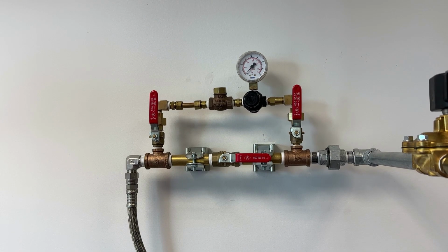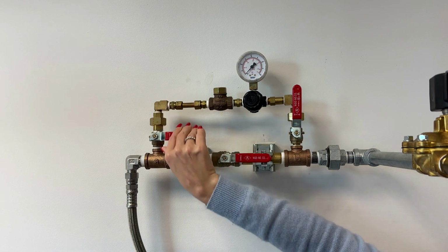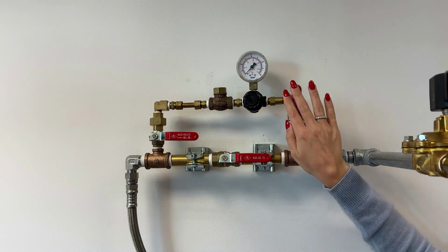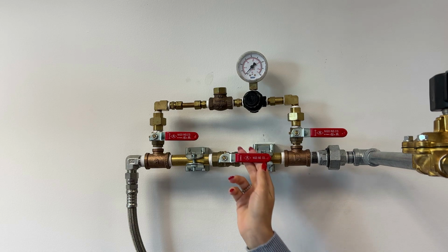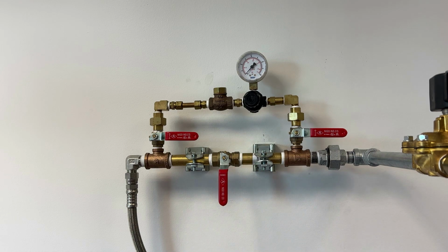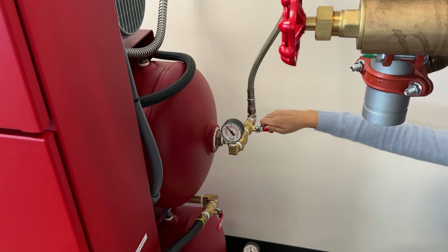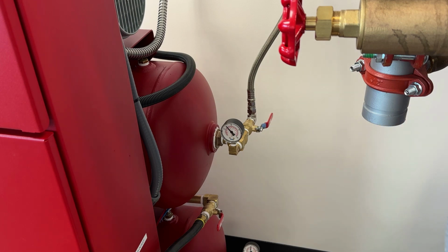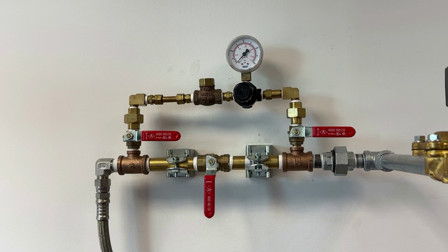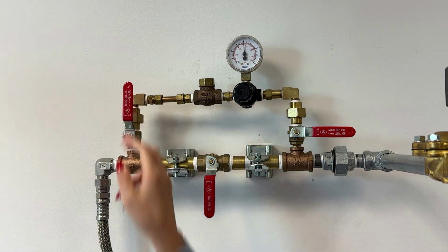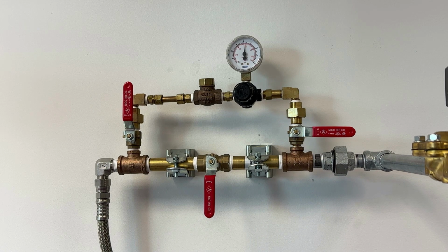Next, close the 1/4-inch regulator inlet ball valve, the 1/4-inch regulator outlet ball valve, and the 1/2-inch bypass ball valve. Then, turn on the automatic nitrogen or air supply. Note, do not pressurize the sprinkler system above the set pressure of the regulator. The regulator is factory set to approximately 40 psi. To check the current setting on the Advanced AAMD, open the 1/4-inch regulator inlet ball valve. Remember, the pressure gauge should read approximately 40 psi.